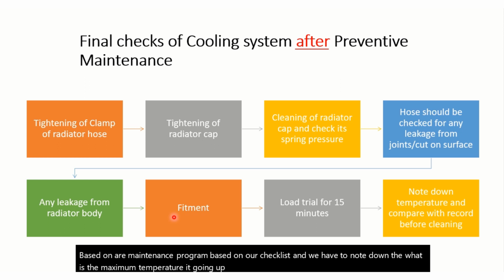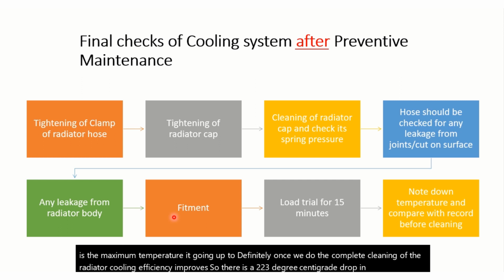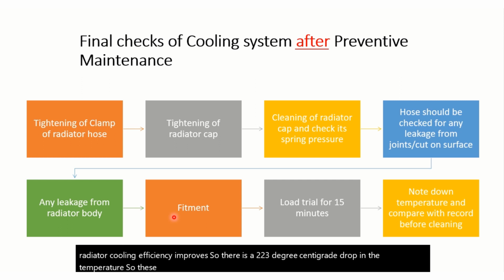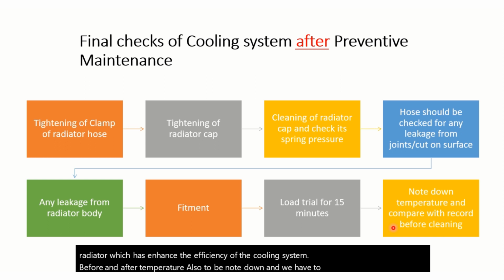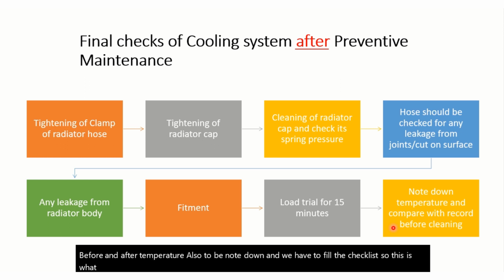Definitely, once we do the complete cleaning of the radiator, cooling efficiency improves, so there is a 2 to 3 degree centigrade drop in the temperature. This drop clearly indicates that it is because of the cleaning of the radiator, which has enhanced the efficiency of the cooling system. So the before and after temperatures should be noted down, and we have to fill in the checklist. This is the entire cooling system preventive maintenance of the DG set.